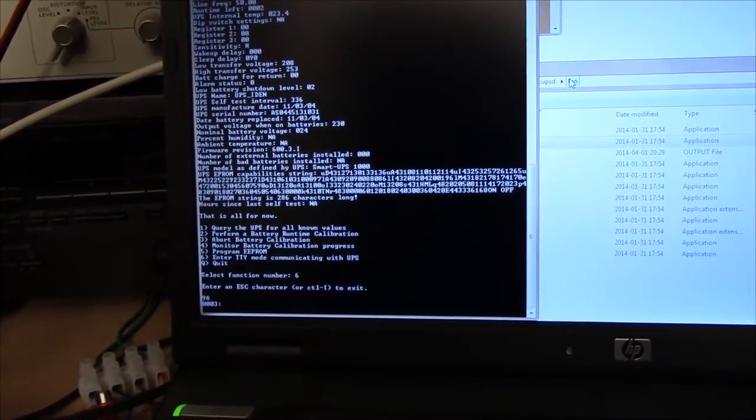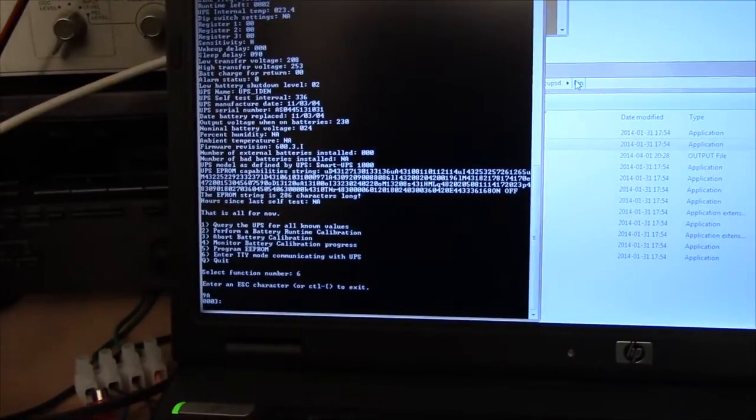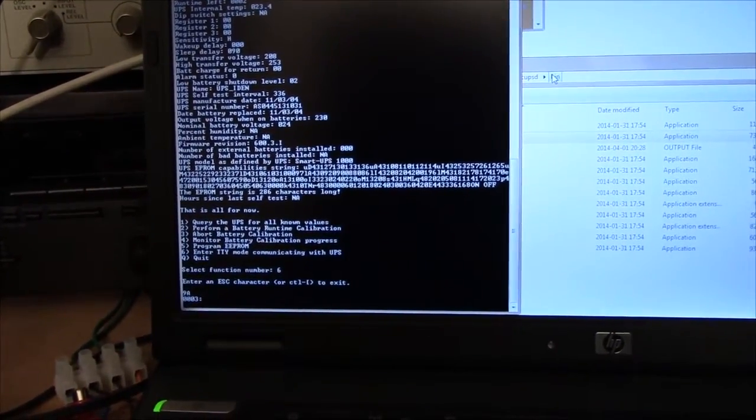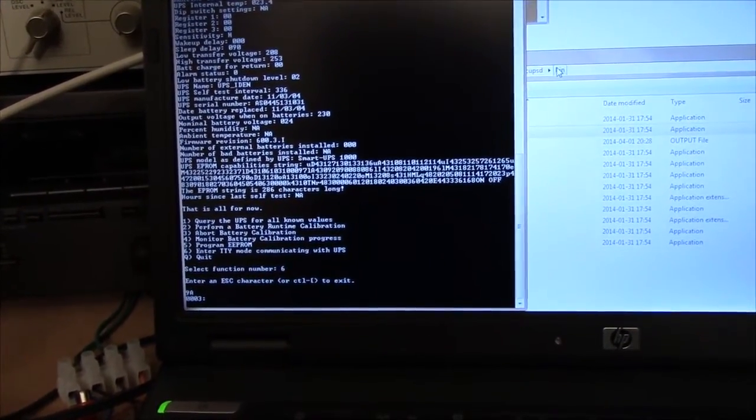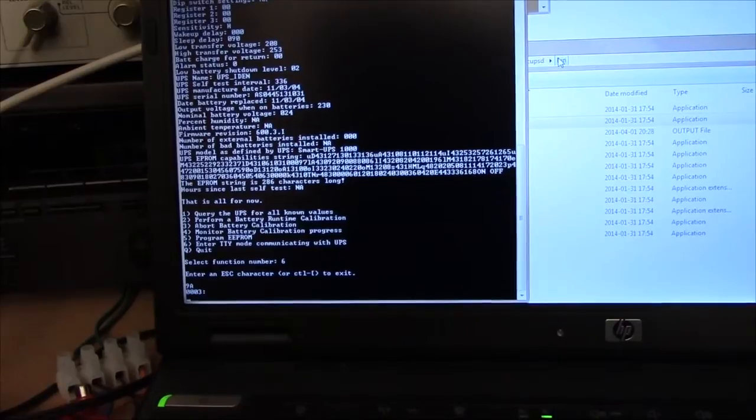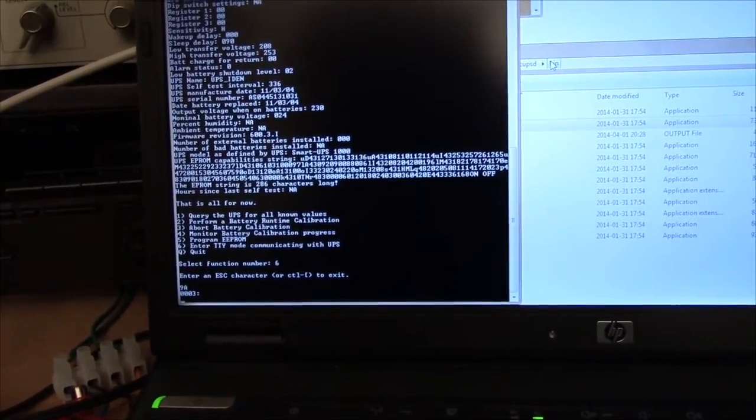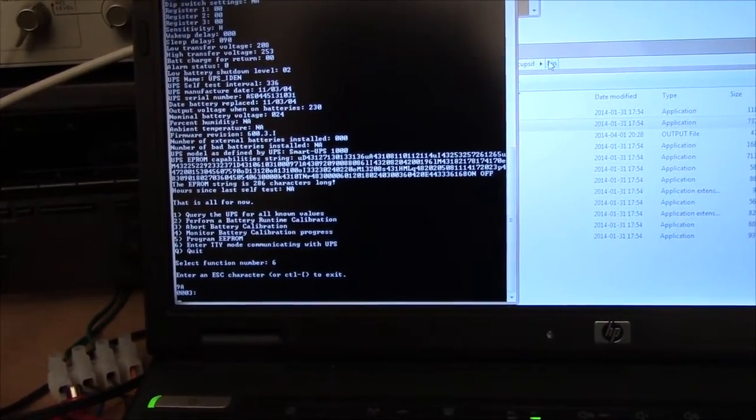The battery calibration just takes care of that little final fine adjustment, which is going to be individual for each set of batteries and each UPS pretty much.